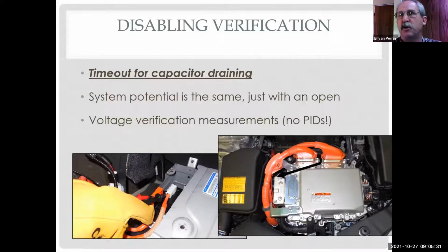Different manufacturers are going to recommend differently. I've seen some programs where they have you do everything with the gloves on, which is just not practical. I'm a big believer—if I know there's no power there, why do I need to wear the gloves? If I work on my panel at the house and kick the big breaker off, and I take my meter and prove there's no voltage going through the breaker and no longer any power in my breaker box at the house, why do I need to wear gloves when I take breakers off or put wires on? There's no power there, I'm safe, right? Where it becomes dangerous is if someone else can turn on the power, or if I just flip the switch and didn't test to make sure the switch worked.